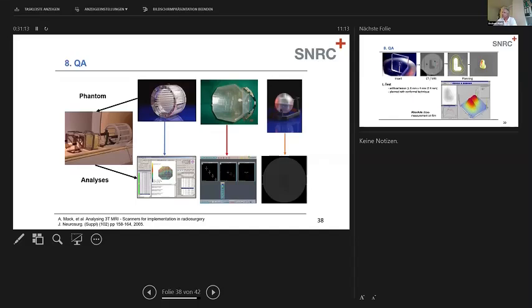So we have these phantoms, and you can put them into either a frame, or you can just put them as a phantom into the MRI scanner. And after the images have been taken and we have analyzed the centers of gravity of these capillary crosses, we go to the application managers, in our case at Siemens, and say, look, these are the deviations which we see. Is there a chance for you to optimize the sequence so that within our stereotactic space of roughly 10 by 10 by 10 centimeters we have an acceptable deviation? And that's what we do. And we manage, even for a 3 Tesla machine, to be below 1 millimeter in all sequences which we use. That takes a certain amount of effort.